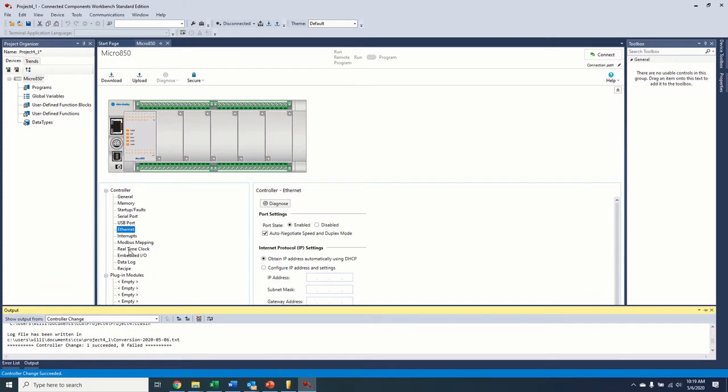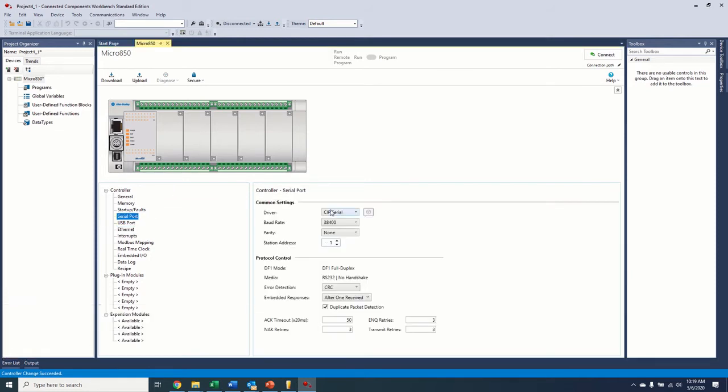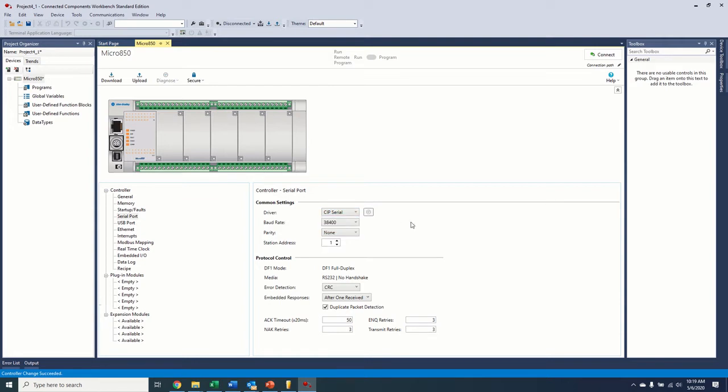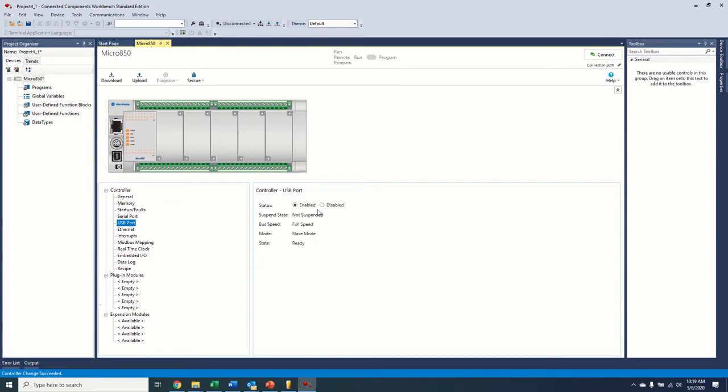And then down here at the bottom, you can see we have a couple other options that showed up because of the controller we selected that were not available on our simulation, one of them being the serial port. So the serial port is just like any other serial port in the past. You do have to set up your baud rate and what your driver is. Is it Modbus? Is it ASCII? Is it serial? And then, you know, what your protocol is. USB, just enable or disable. As we know, USB does not need any configuration, so if we're going to enable it or disable it, you can use the USB port for programming, monitoring, firmware, flashing, things like that. So if you don't want somebody to be able to come up and plug into the controller and get online with it, you can just disable the USB port.